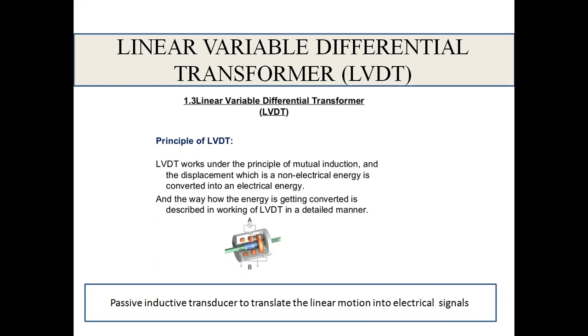Now about the construction of the LVDT. The transformer consists of a single primary winding P and often two secondary windings S1 and S2, wound on a cylindrical former. A sinusoidal voltage of amplitude 3 to 15 volts and frequency 50 to 20,000 hertz is used to excite the primary.